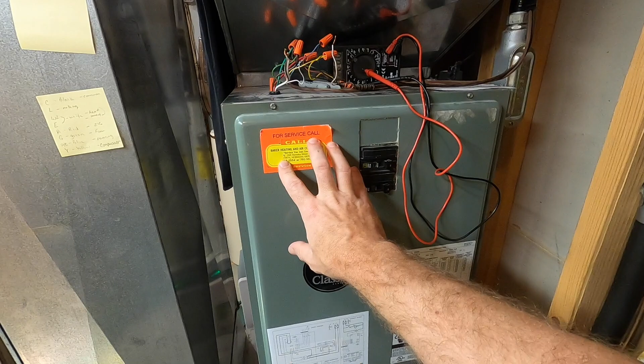Now we've already been up to the thermostat. We know that we're getting that current on the white wire. We just have to figure out where it's coming from. But just because we're detecting it at the thermostat does not mean it's coming from the thermostat, because those wires are connected down here. So here's the white wire from the thermostat. Here's the white wire from the outside condenser unit. And then here's the white wires. There's actually two of them on this unit that go inside to the control board in here. So we need to figure out if the electricity is coming on this one, or coming on this one. If it's neither of those, that means that somewhere in this control board it's telling it to bring on the auxiliary heat when it doesn't need to.